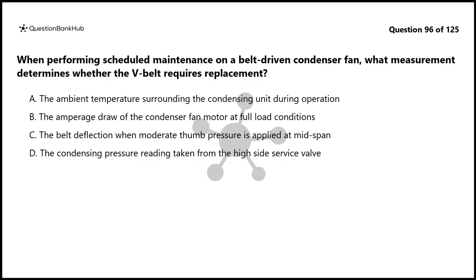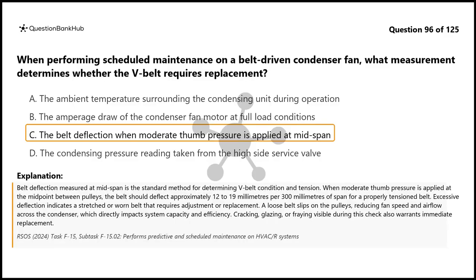The correct answer is C. Belt deflection measured at mid-span is the standard method for determining V-belt condition and tension. When moderate thumb pressure is applied at the midpoint between pulleys, the belt should deflect approximately 12 to 19 mm per 300 mm of span for a properly tensioned belt. Excessive deflection indicates a stretched or worn belt that requires adjustment or replacement.